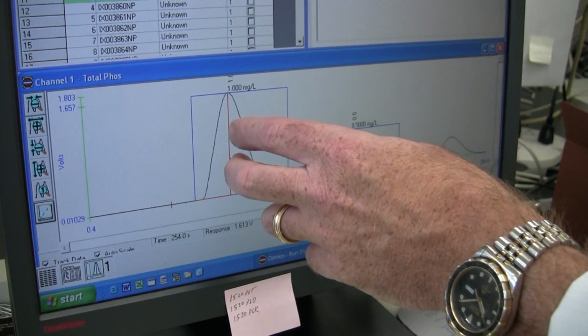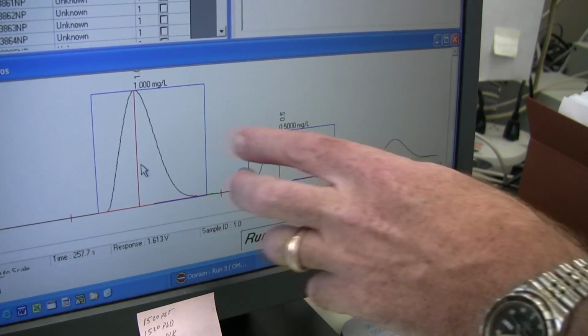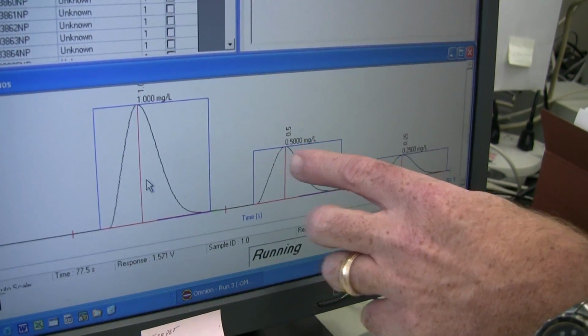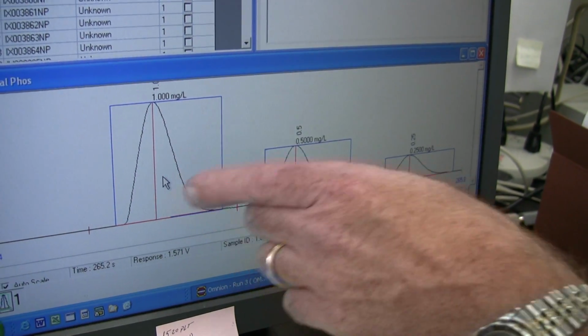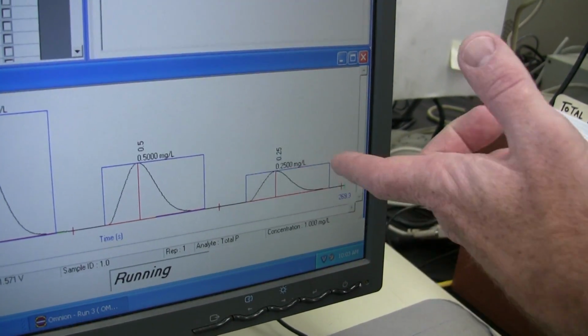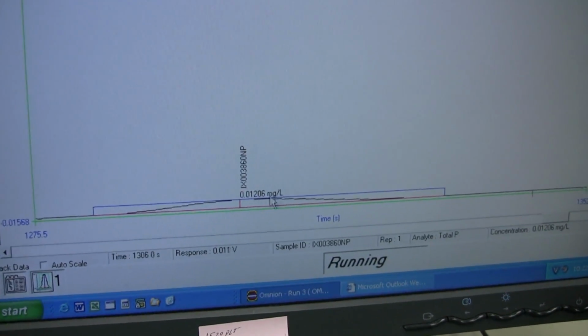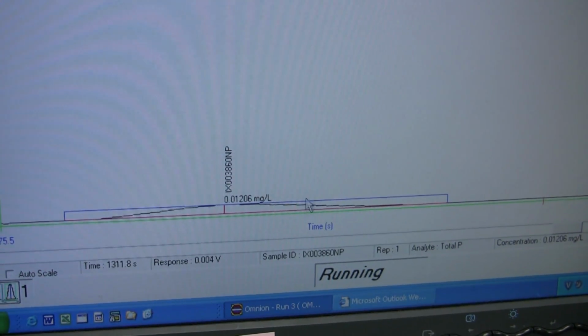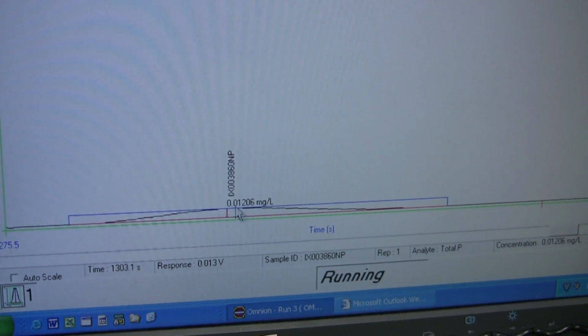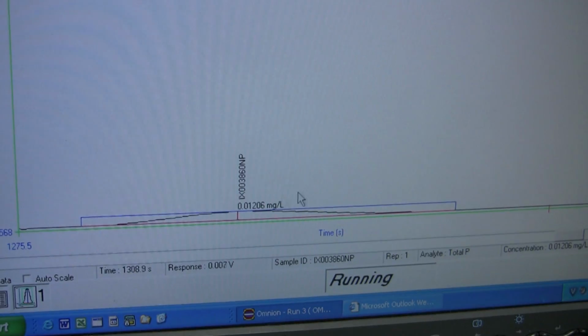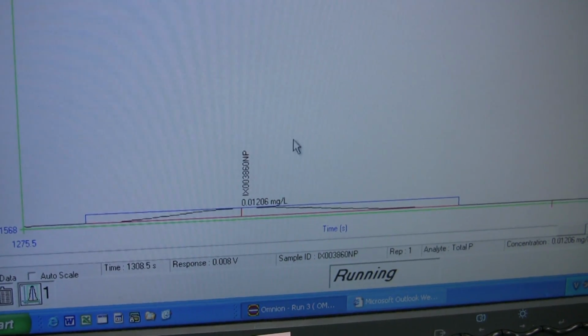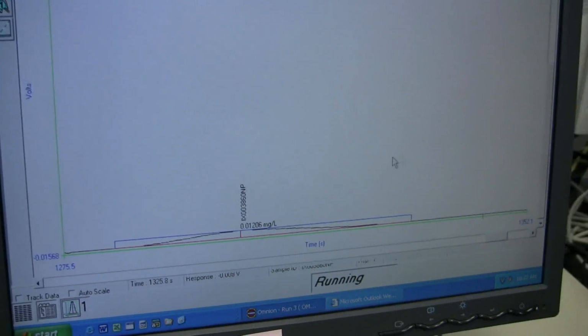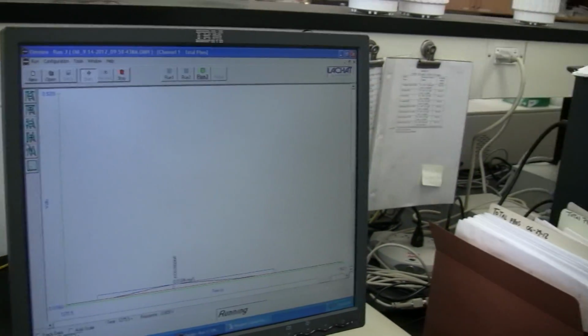Right. Basically, this is more blue. This is actually half as blue because this is one part. This is half a part of phosphorus in the standard. This one has twice as much, half as much. This is half again because we're down to 0.25. So if we were to look at these in test tubes, it'd be blue, half as blue, half as blue again, basically. I can't hardly see the number, but 3860 is the sample number, and it has 0.012 milligrams per liter phosphorus. And so that'll go along, and as each unknown has its peak area, we'll be able to give it a concentration of phosphorus, because we did run that curve of known concentrations and figured out that calibration, and then we'll be able to figure out all of our samples for the day.